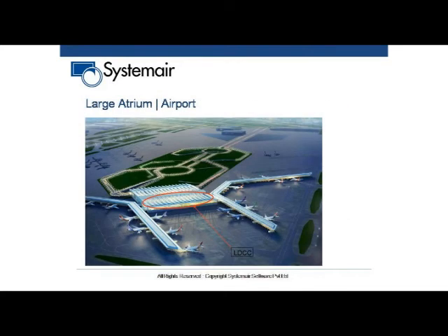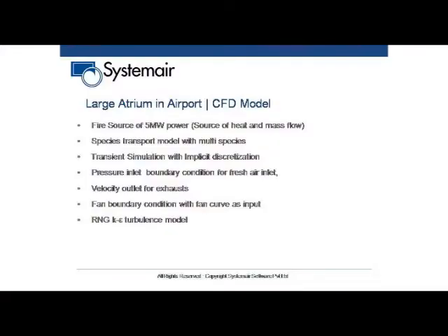This is an upcoming international airport, a new airport in New Delhi, and there is a large atrium where there are check-in counters in each area. We did a simulation with a 5 megawatt source of fire. 5 megawatt is typically a car fire, or maybe a bit more than that, so it was a reasonable size of fire. Species transport, these are the CFD terminologies that we used for that particular case.